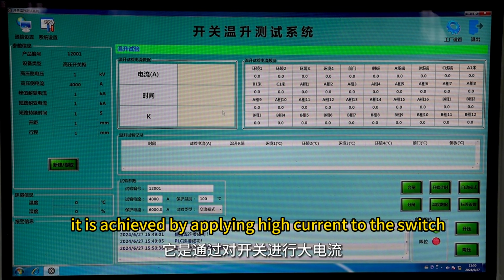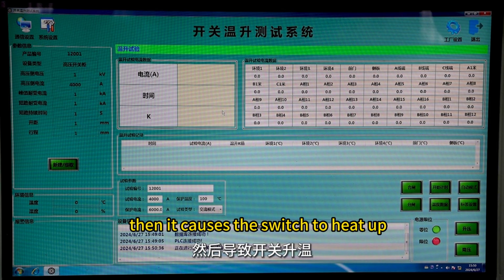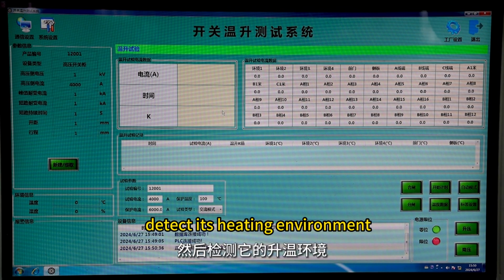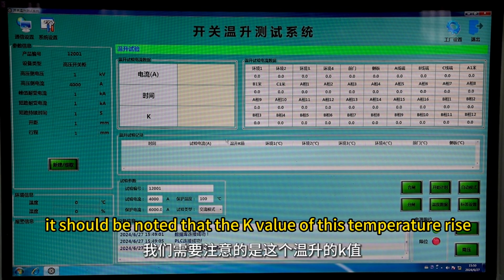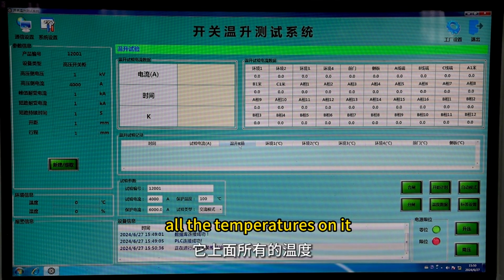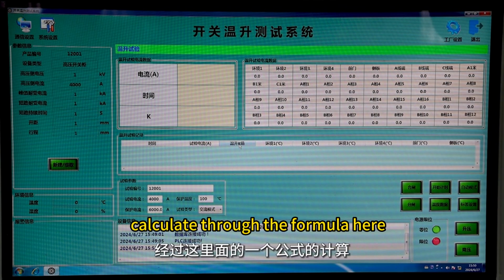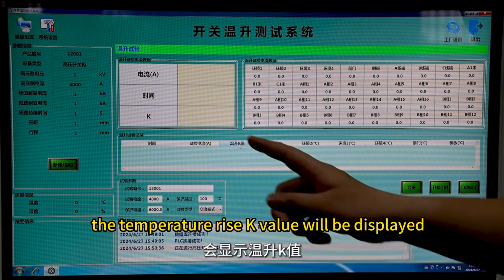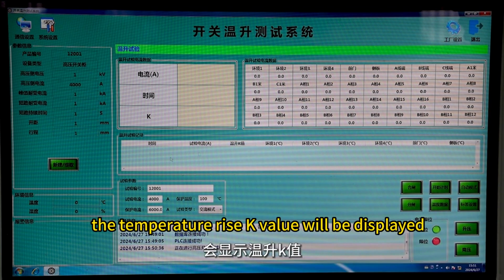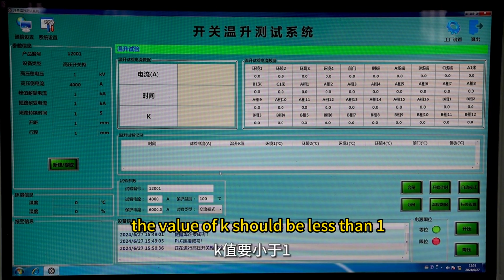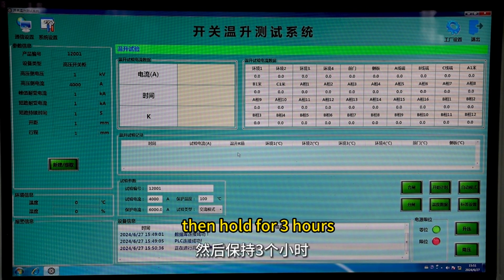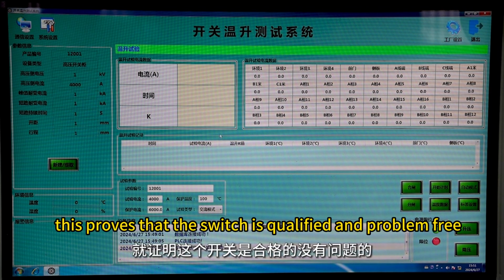It is achieved by applying high current to the switch. Then it causes the switch to heat up, and the heating is detected. It should be noted that the K value of this temperature rise is calculated from all the temperatures on it through the formula here. The temperature rise K value will be displayed. The value of K should be less than 1, then hold for 3 hours. This proves that the switch is qualified and problem-free.